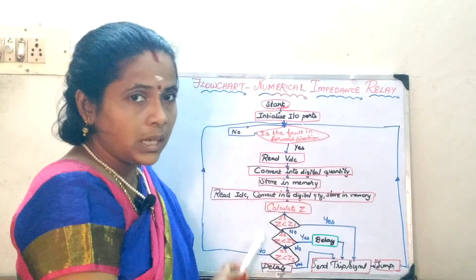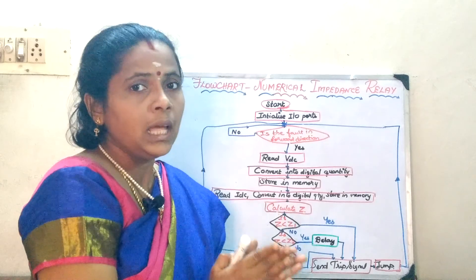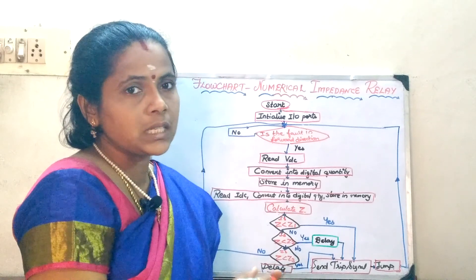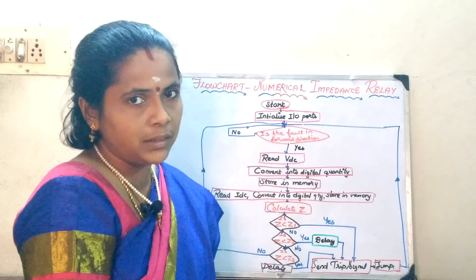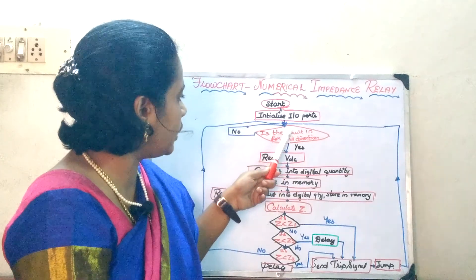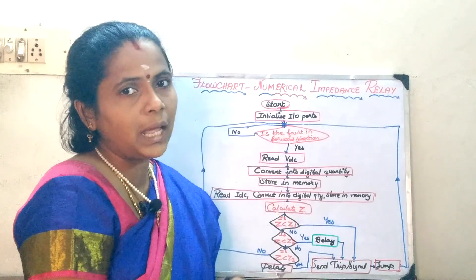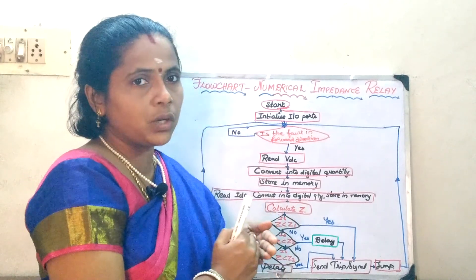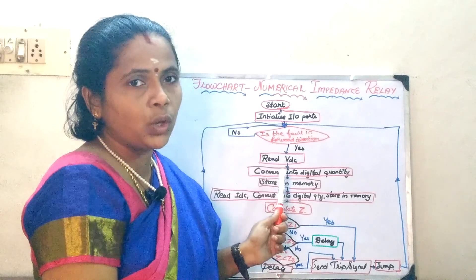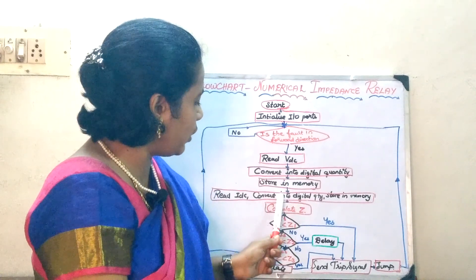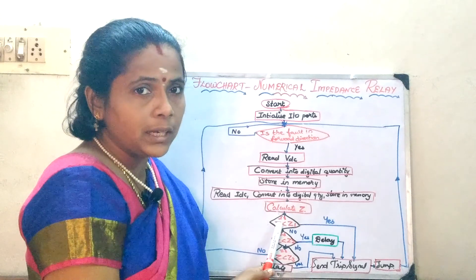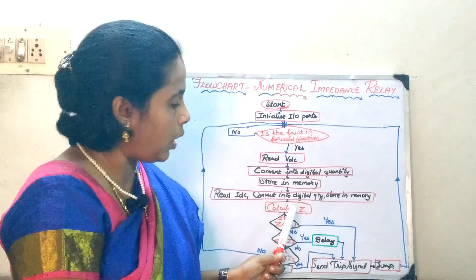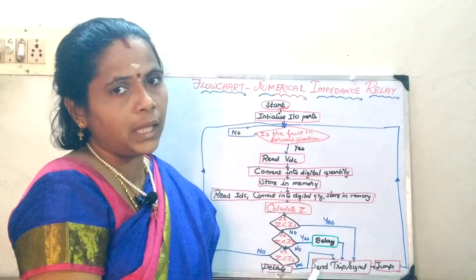Suppose these conditions do not occur — that is, only if there is a fault will the impedance be less than the required value, namely Z1, Z2, or Z3. If Z is going to be greater than Z3, it jumps back and checks whether the fault is in the forward direction and then proceeds. So we find the direction of the fault, proceed with VDC and IDC, check the V/I ratio, and if there is a fault, the fault impedance will be less than Z1, Z2, or Z3 accordingly, and the tripping action will be carried out.